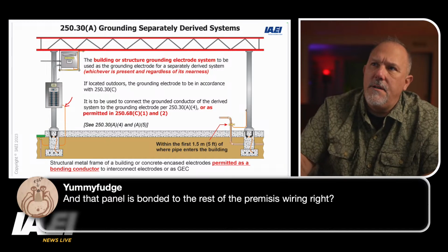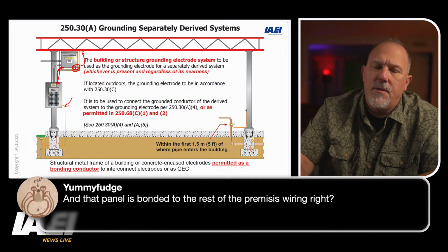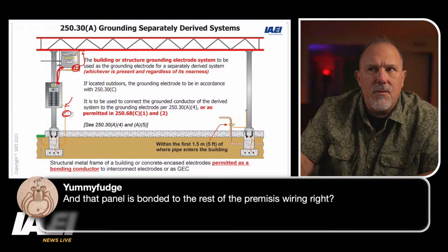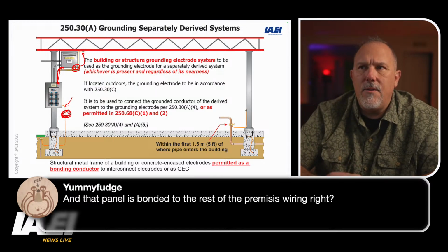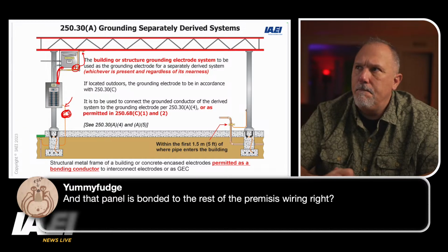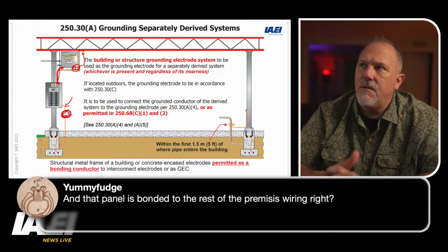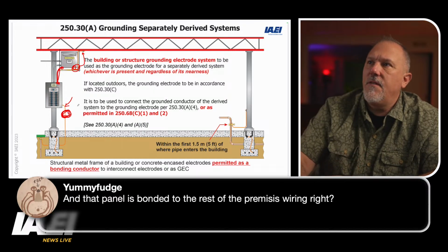If I'm bonded from here to here, and this establishes my equipment ground, so this is bonded, and this is bonded, and there's a bond here going to the grounding electrode system, I'm not sure I have a code requirement that says I need to ground that panel board and bond that panel board and take it to a grounding electrode conductor. The building or structural grounding electrode system to be used as the grounding electrode for the separately derived system, whichever is present, there it is.